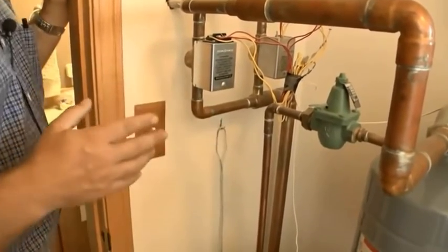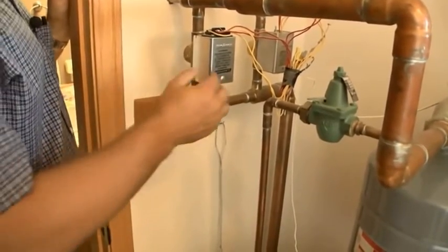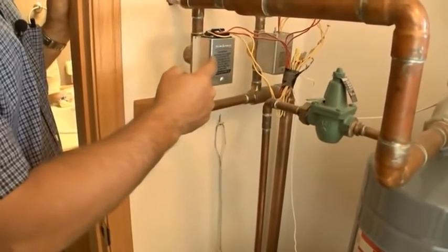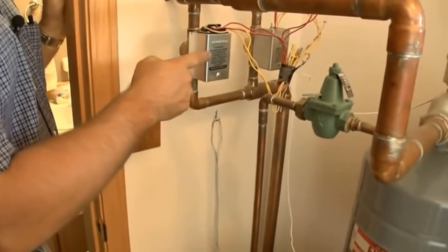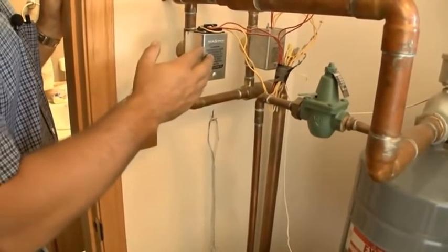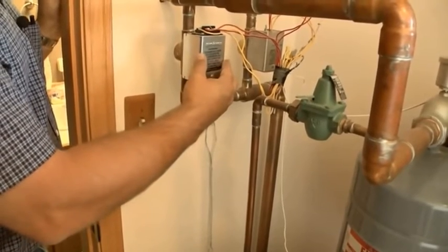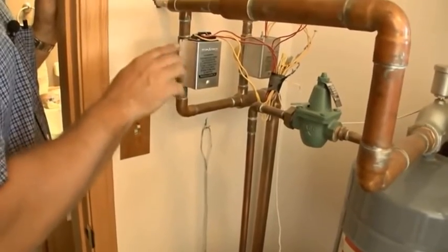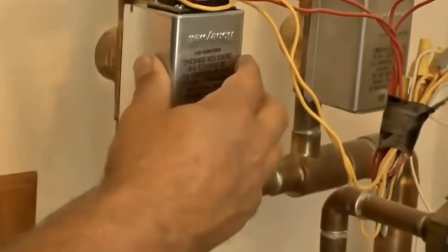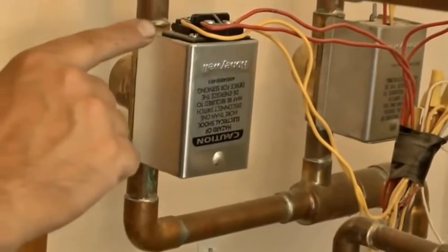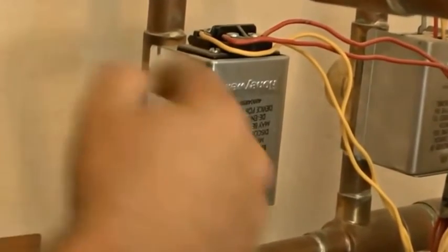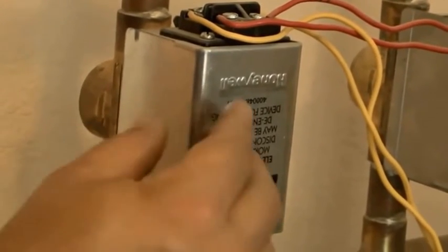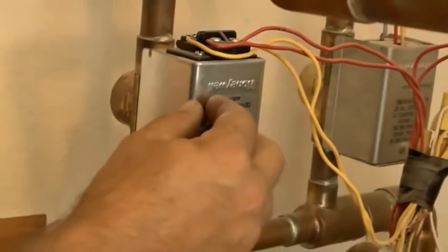Or one zone could be calling, and the water is being pumped through that one zone. If you have a mechanical thermostat, you set the heat anticipator on the mechanical thermostat to the amperage draw of the zone valve. On a forced air furnace, you typically set it to the amp draw of the gas valve. That's one of the differences with multi-zone pieces of equipment, is you set it to whatever device the thermostat is controlling. In this case, the thermostat controls the zone valve. It allows the motor in the zone valve to open the valve.